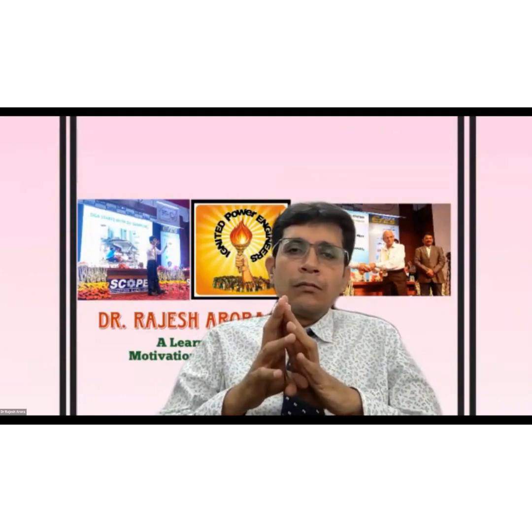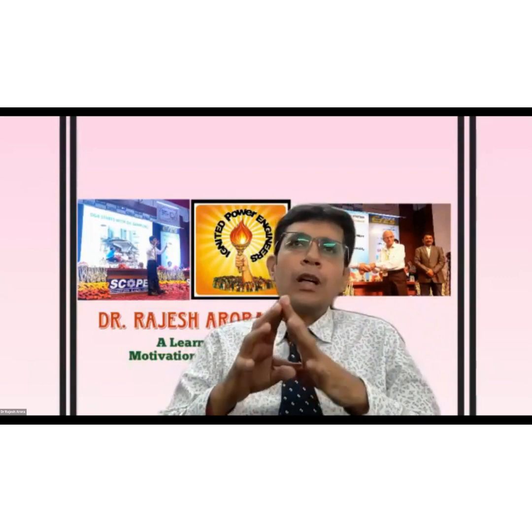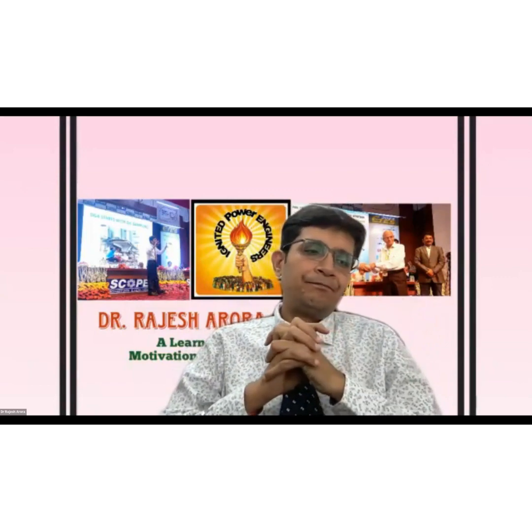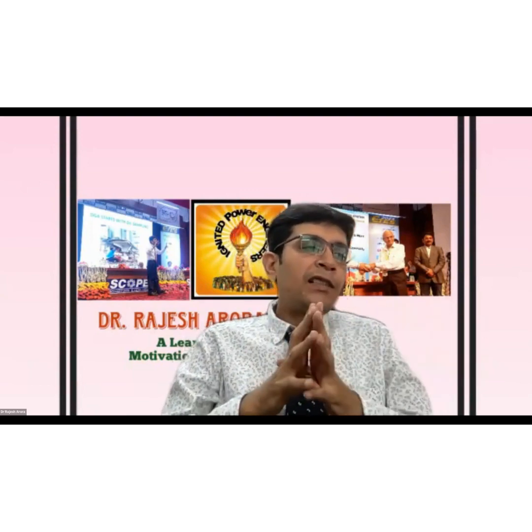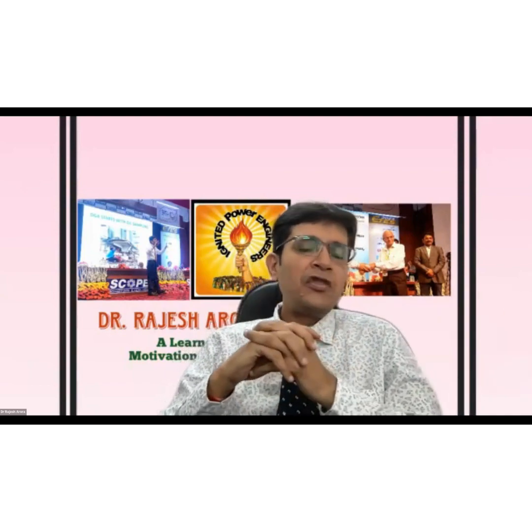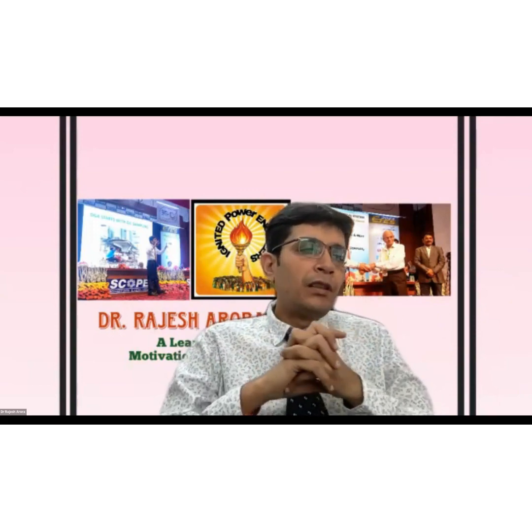But what I have noticed is that many manufacturers in India are still giving transformers with PI values of above 1.5. They need to change the specification. They need to understand the drying out methods at site prescribed by the CEA standard specification, which include vacuum, dry nitrogen gas filling and heating methods.